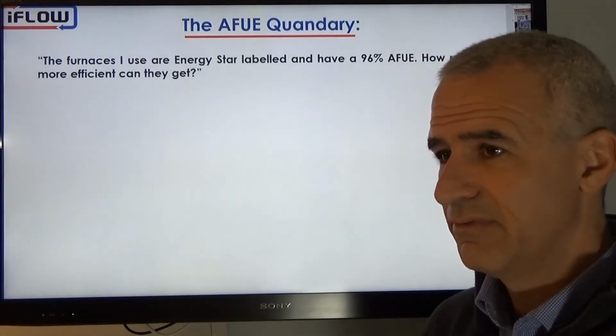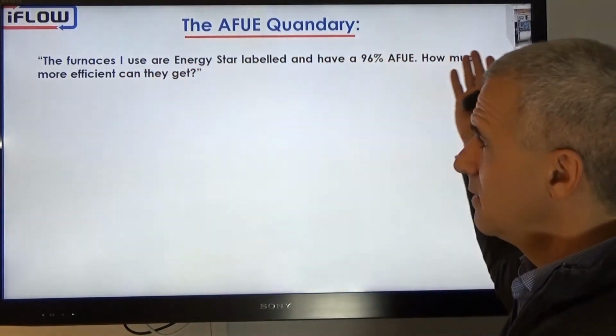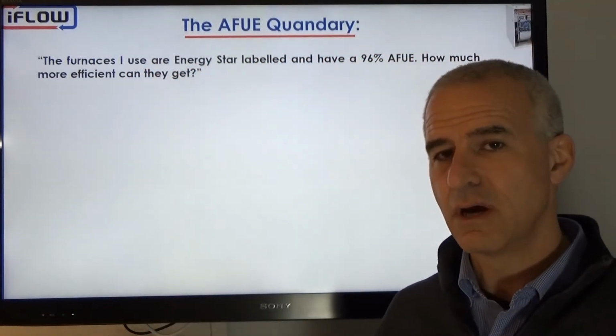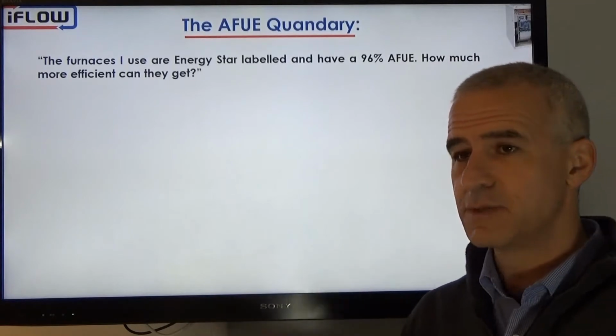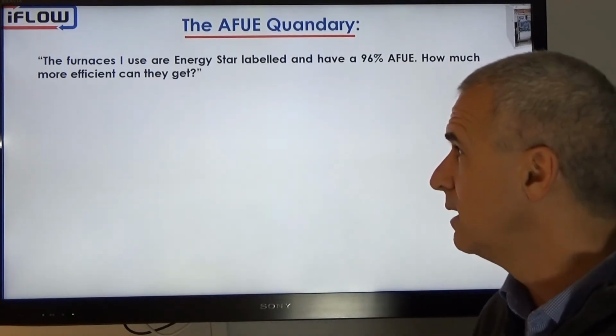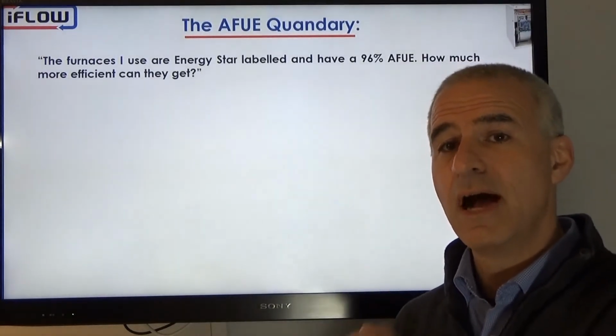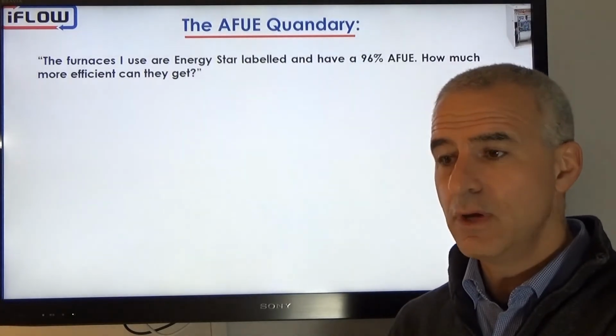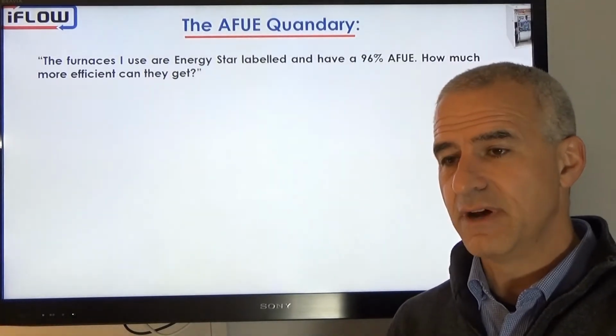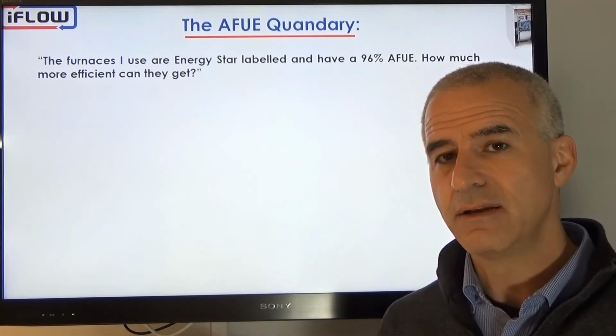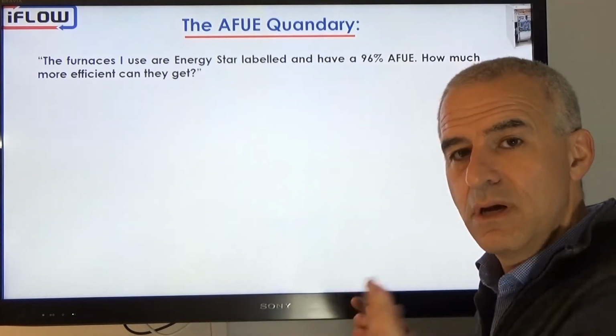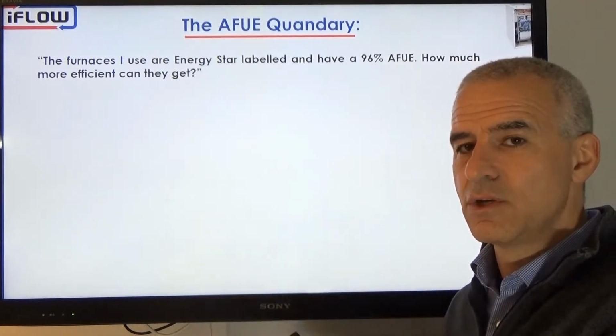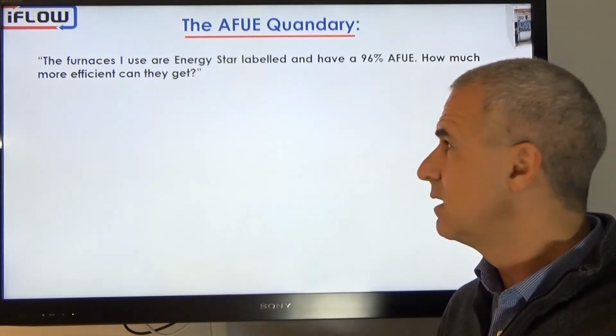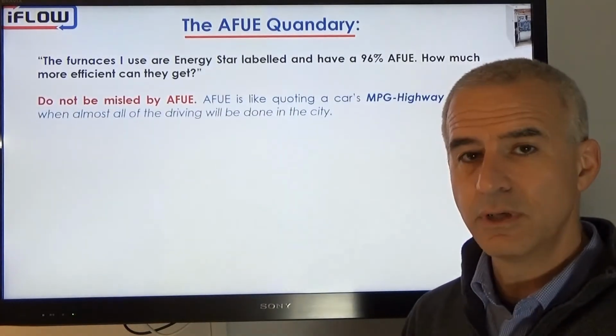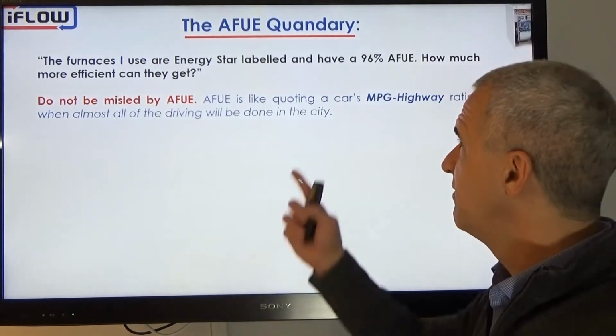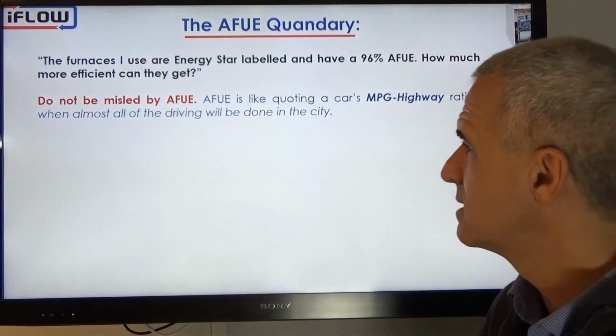So we get this often, right? The furnaces that I use are already Energy Star, you know, they're 98%, 96%. How much better can it really be? Well, we just saw the curve, how much better it can be. You can have a single stage 95% AFUE rated furnace, but we saw the single stage, you're going to be cycling so much more on today's homes that your performance is going to be much, much lower than the 95% stated AFUE or 96% stated AFUE.